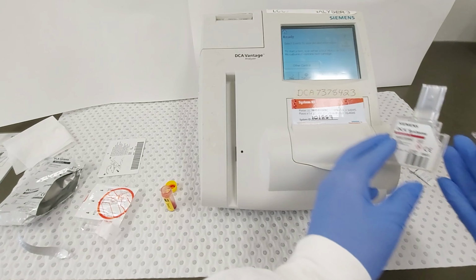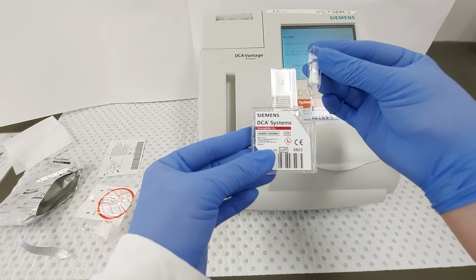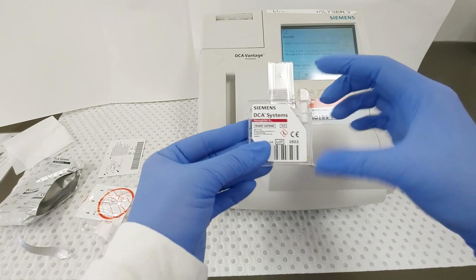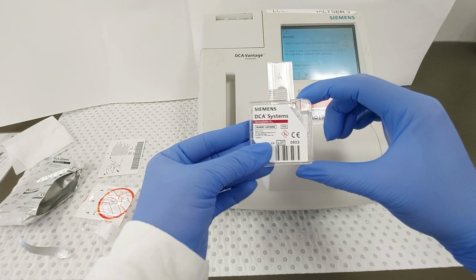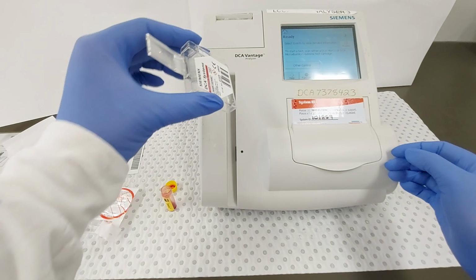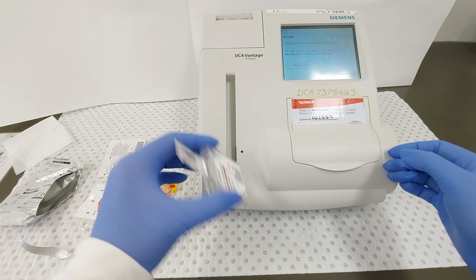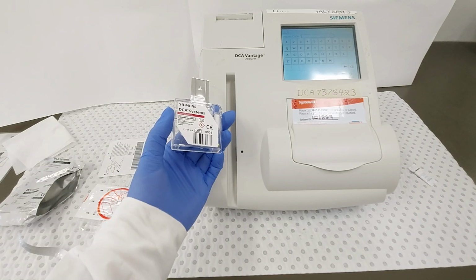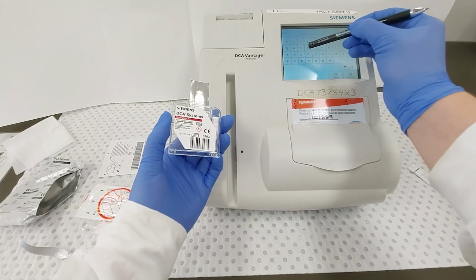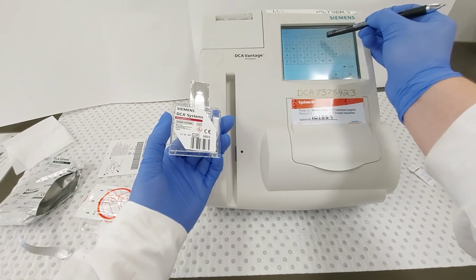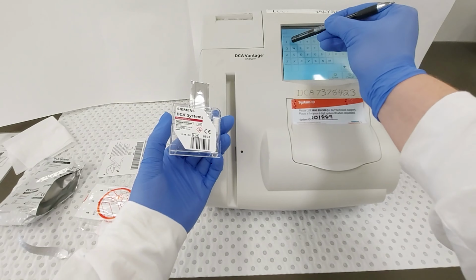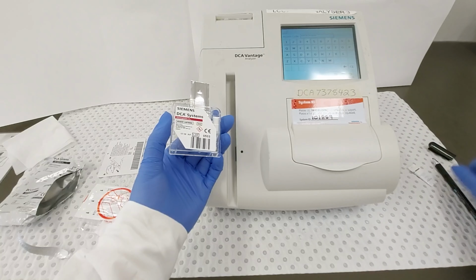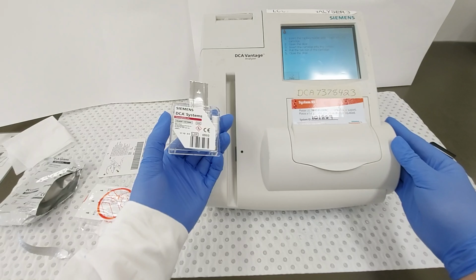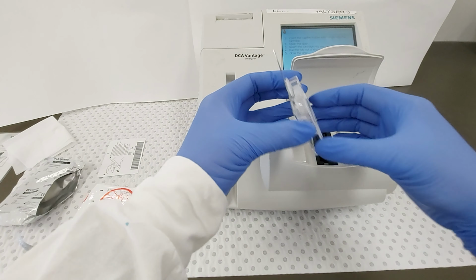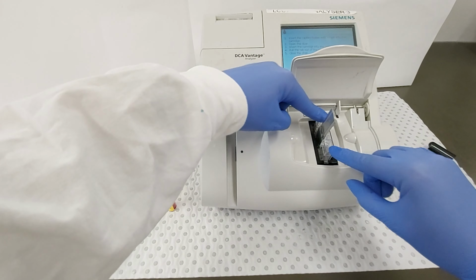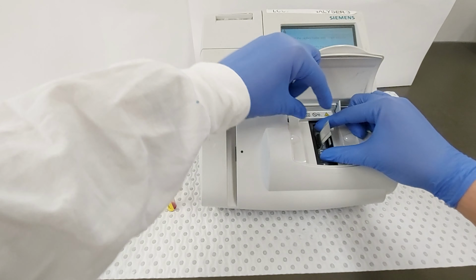Orienting the upper curved edge of the capillary outwards, snap the capillary into the reagent cartridge. Scan the reagent cartridge and capillary tube assembly in the onboard barcode reader. Now enter the access code using the display screen, either with your finger or with a stylus. The access code will be an individual code for each user that will be set up in advance. Once the access code is accepted, insert the reagent cartridge into the reagent cartridge compartment with the barcode facing to the right until an audible click is heard.